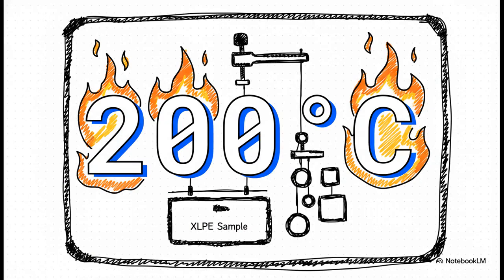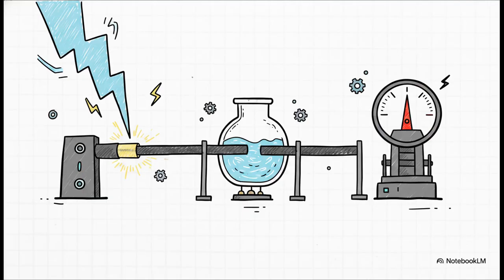And just how hot is that high heat in the hot set test? Try 200 degrees Celsius. They literally bake the XLPE sample at 200 degrees while hanging weights from it just to ensure its thermosetting properties hold up. It's a pretty brutal demonstration of resilience for sure. And honestly, that's just one test. These cables also have to survive high voltage dielectric withstand tests to make sure they can handle extreme power surges. They go through insulation resistance testing, where XLPE consistently hits the massive giga-ohm range, pretty much blowing PVC out of the water. For higher voltages, they even run tan delta tests and check for microscopic water trees that could degrade the insulation. Only the absolute strongest survive the factory floor.